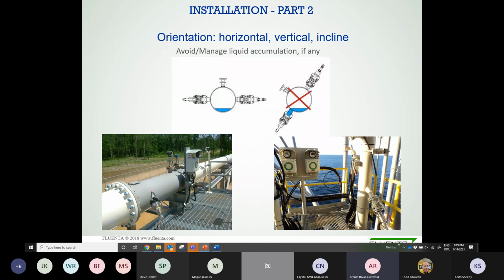So I'll show you a couple of installations, onshore, offshore, with different orientations, for example. You see a horizontal pipe. In this one, you see a vertical pipe. These ultrasonic meters can be installed in both directions, but there are also some considerations in case you may see some kind of liquid or condensation in the pipe, especially at that point when you're flaring.